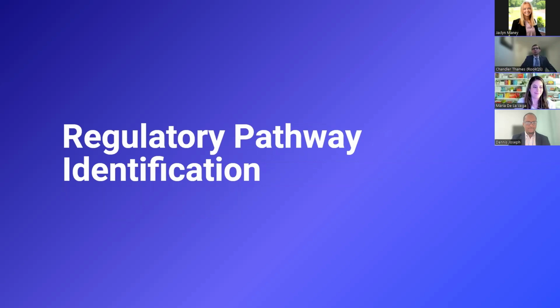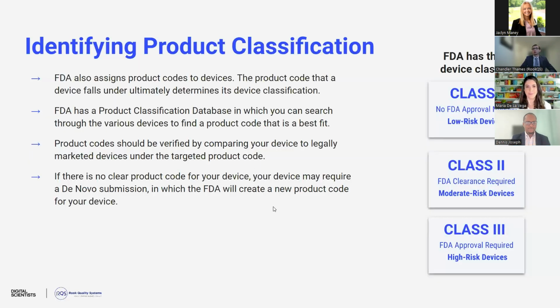Thanks, Maria. So we'll first touch on regulatory pathway identification. This is something that's very critical because ultimately it's going to determine how your device is brought to market and whether your device can be brought to market. So in terms of US FDA, they have a process for identifying product classification where they assign product codes to devices. When you compare it to the way that Canada and the EU does this, they have very strict product classification rules where if this applies to your product, it falls in this class. FDA does it a bit differently.